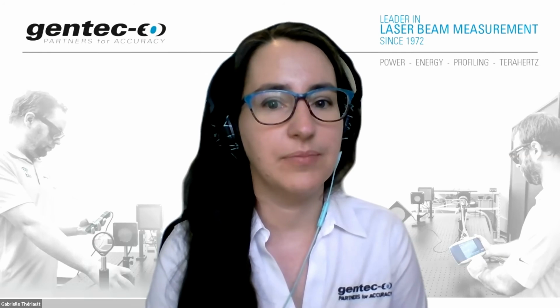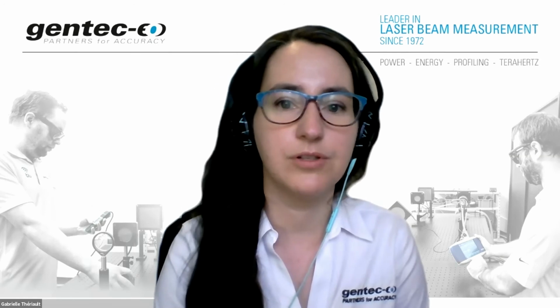Now, if you're measuring pulse lasers, are there any things you should watch out for compared to continuous wave lasers, if what you want to measure is the average power? Okay. If you have pulse lasers, you can measure three things. First could be beam profile. Second could be pulse-to-pulse energy. Each given laser pulse will provide an amount of energy in joules, and you can measure that using pyroelectric detectors, not the thermopile detectors.